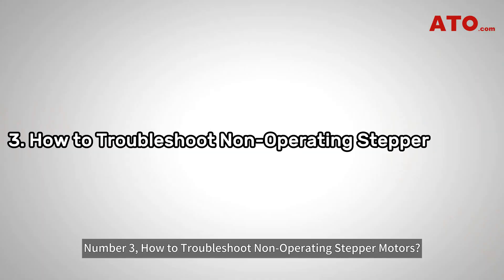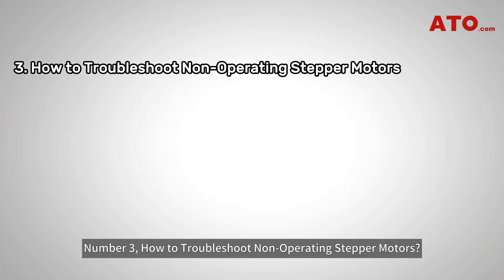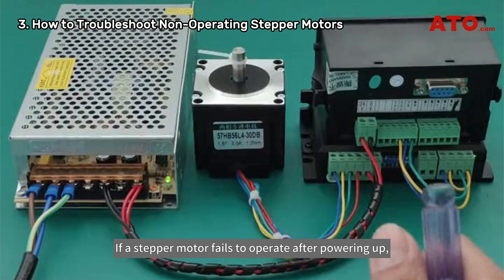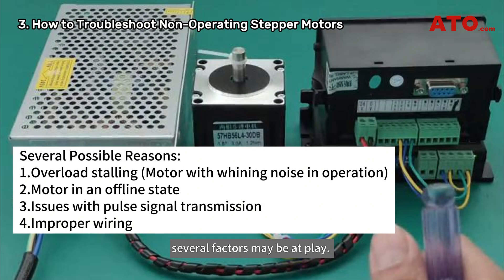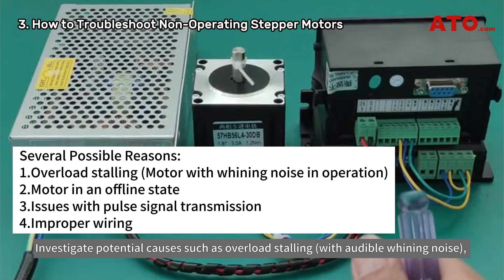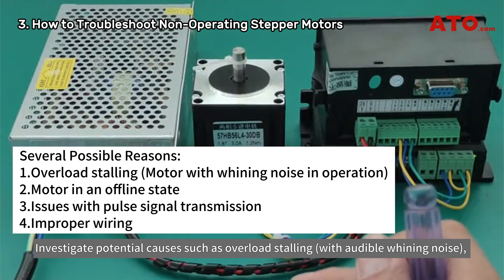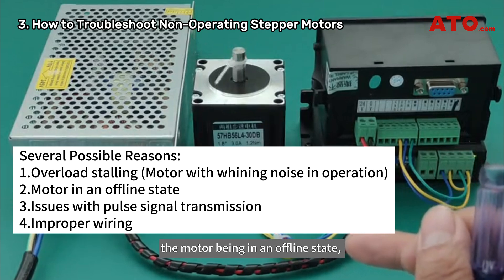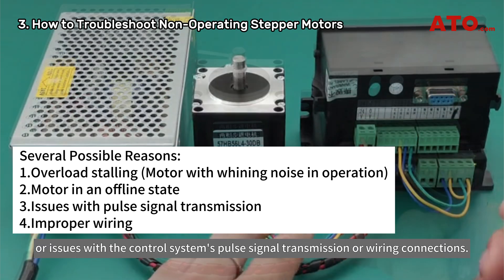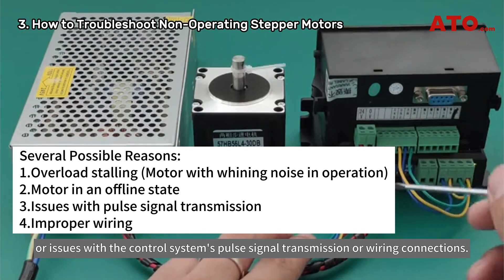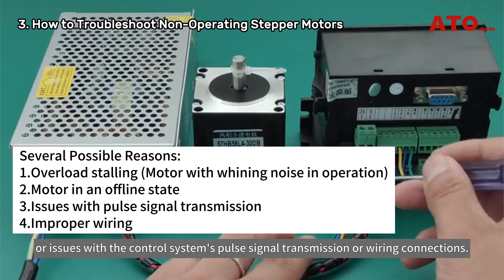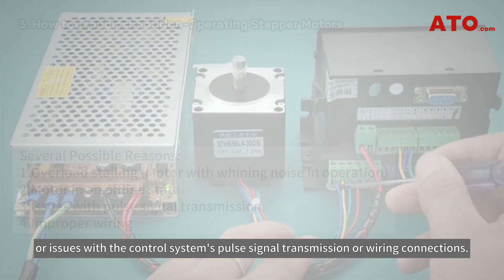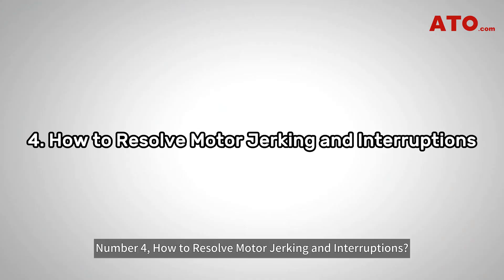Number three: how to troubleshoot non-operating stepper motors. If a stepper motor fails to operate after powering up, investigate potential causes such as overload stalling with audible whining noise, the motor being in an offline state, or issues with the control system's pulse signal transmission or wiring connections.